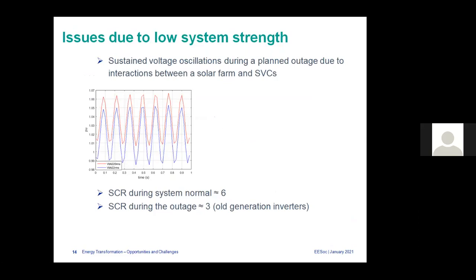So what the operators did was immediately put the SVC in manual mode. That settled it and removed the oscillation, because when both are in automatic control mode trying to control the voltage, they can interact. But if you bring one into manual mode, that interaction will go away. What we found later is you can model this. When we create a PSCAD model of the system, under system normal operation you don't see this oscillation, but when you take one line out in the model, you see it. So these can be easily modeled and seen.